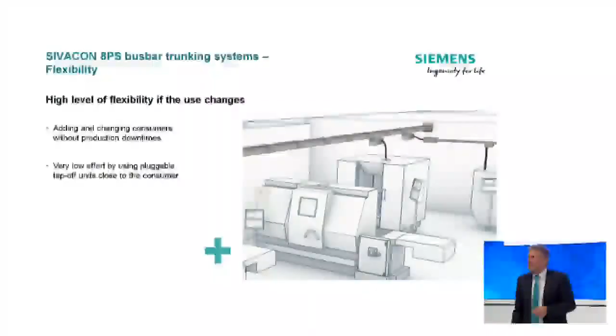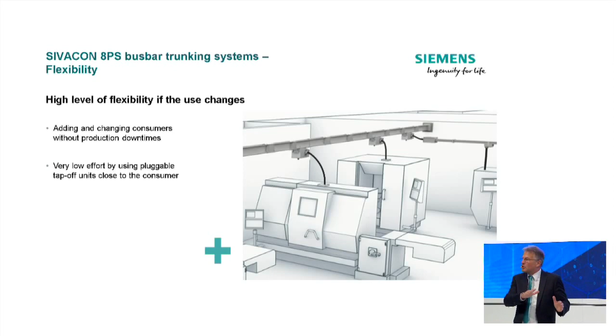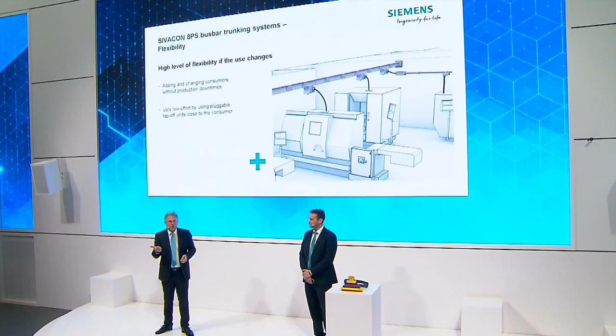With a busbar trunking system, you can adapt a new machine very easily and very quickly. Our tap-off units can be plugged in, removed, replaced, or extended under an energized bus run. That means you don't have to switch off the bus run, all other machines keep running. The advantage for you: no downtime and very little effort.